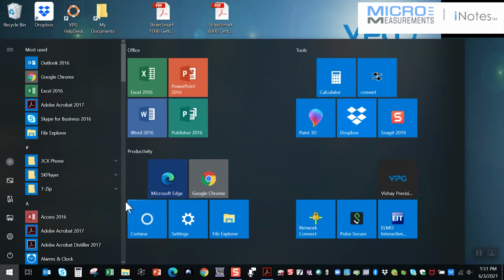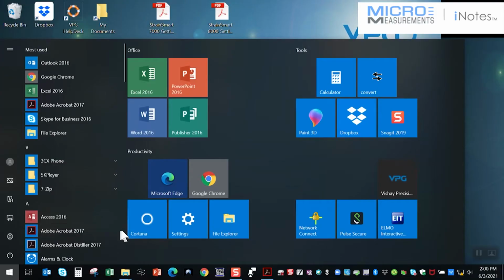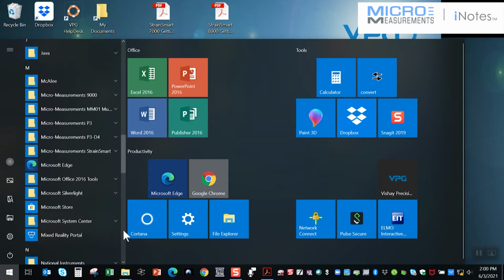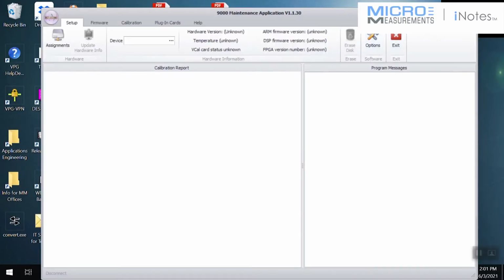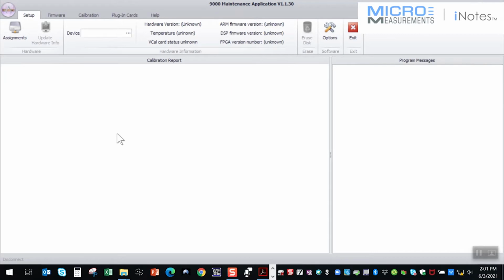And that probably took maybe 20 seconds to install the maintenance utility. So now what we're going to wind up doing is go into the maintenance utility that we just installed. And that's located right here. This maintenance utility allows you to configure the scanner. Since it supports DHCP, about the only thing you have to do is go out and find it.